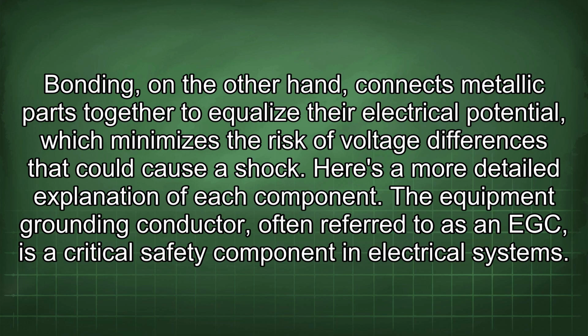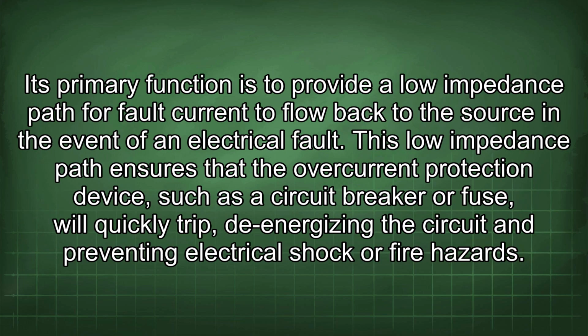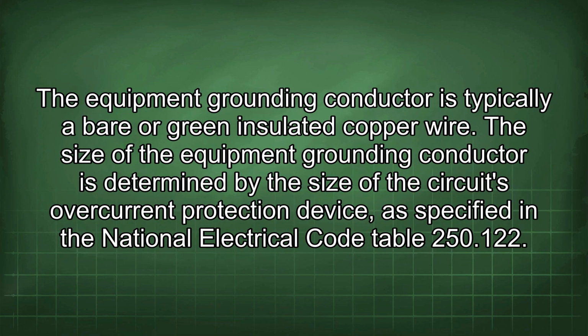The equipment grounding conductor, often referred to as an EGC, is a critical safety component in electrical systems. Its primary function is to provide a low impedance path for fault current to flow back to the source in the event of an electrical fault. This low impedance path ensures that the overcurrent protection device, such as a circuit breaker or fuse, will quickly trip, de-energizing the circuit and preventing electrical shock or fire hazards. The equipment grounding conductor is typically a bare or green insulated copper wire.